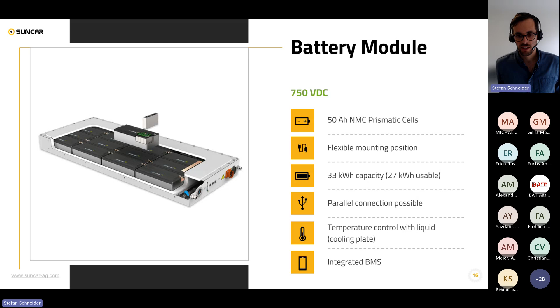If you have multiple batteries installed in parallel operation, a battery can be reconnected automatically as a hot-sync feature, for example, to synchronize it again on the high voltage bus once it's free of any failure. We're seeing a big need for high redundancy and the best uptime in these applications, which is what we're trying to engineer our solutions for.